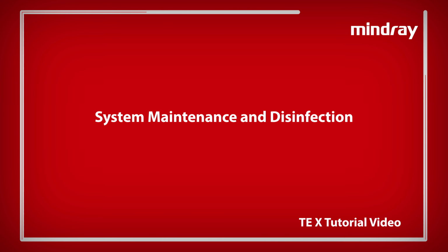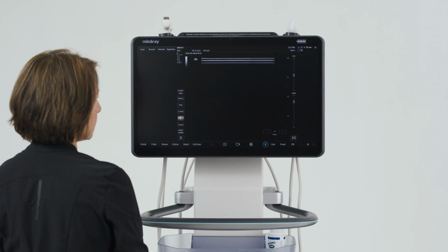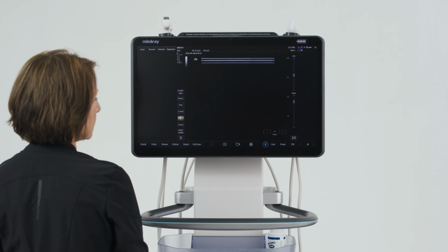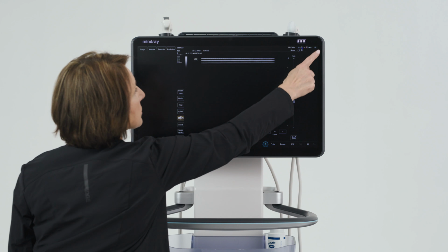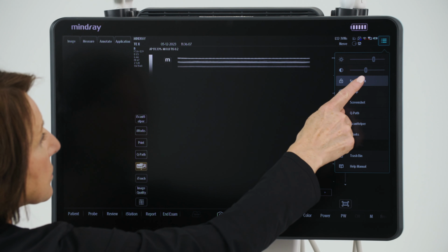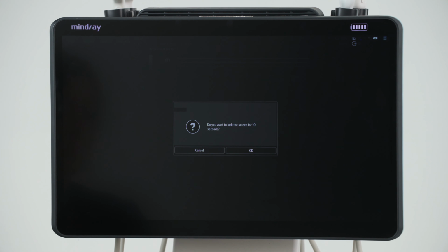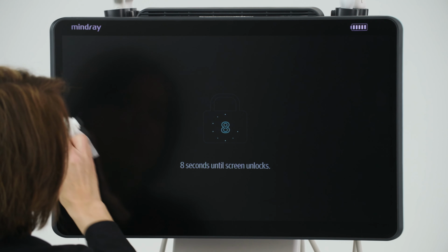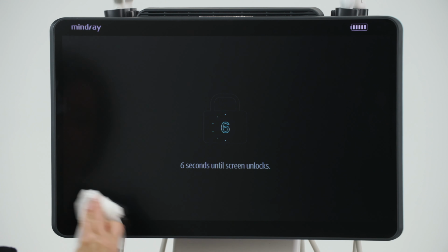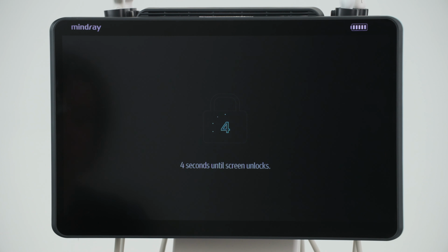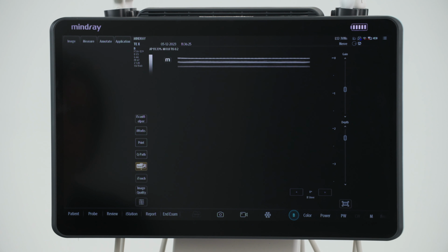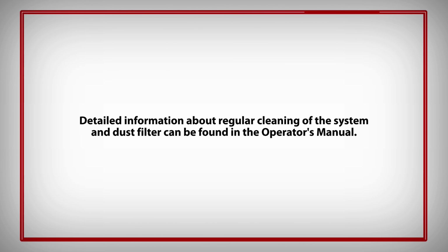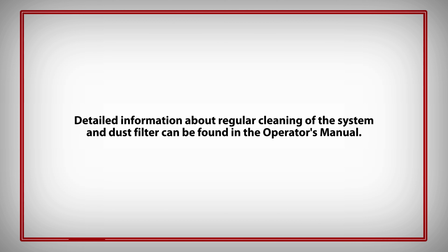System maintenance and disinfection. The TE X screen is easily cleaned and disinfected using an approved product. To clean the screen without changing any imaging parameters, select the menu button in the top right corner of the imaging screen. Select Screen Lock. This will lock the screen for 10 seconds in order to clean the screen without accidentally changing any settings on the system. Please reference the provided disinfection and sterilization guide or contact an application specialist with any questions concerning system disinfection. Detailed information about regular cleaning of the system and dust filter can be found in the operator's manual.